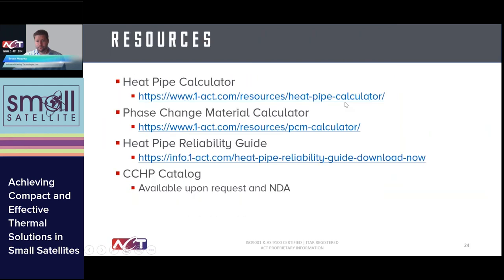We'll send this presentation out and post the recording. We have several design resources available. The heat pipe calculator is a free online design tool hosted on our website that helps you size copper-water heat pipes — it outputs a transport curve showing how much power you can move at various temperatures and diameters, a great first-order tool. We also have a phase change material calculator using high-level principles to size PCM, giving options based on various melt temperatures. If you get close using those calculators, contact us and we can help optimize your design. We also have the reliability guide available online covering the extremes testing our heat pipes have undergone.